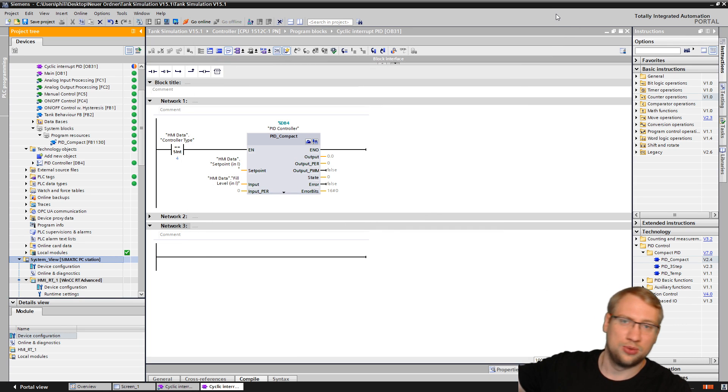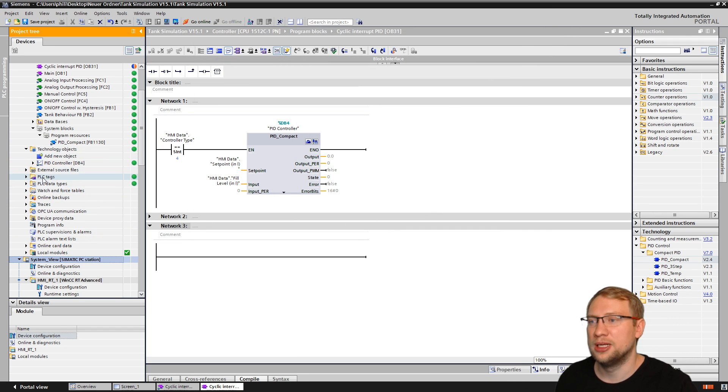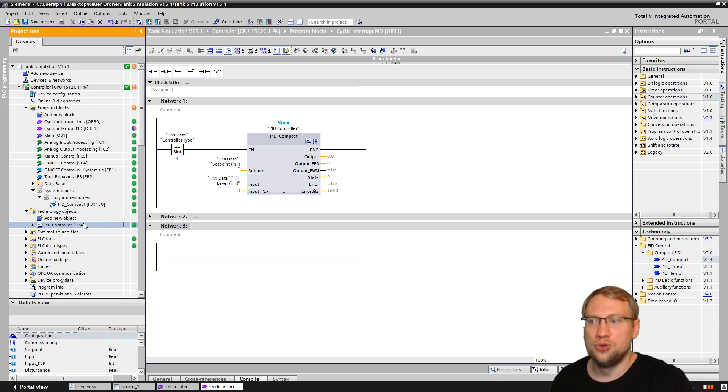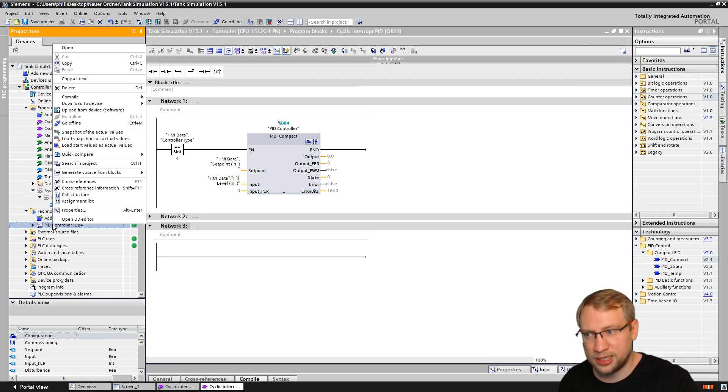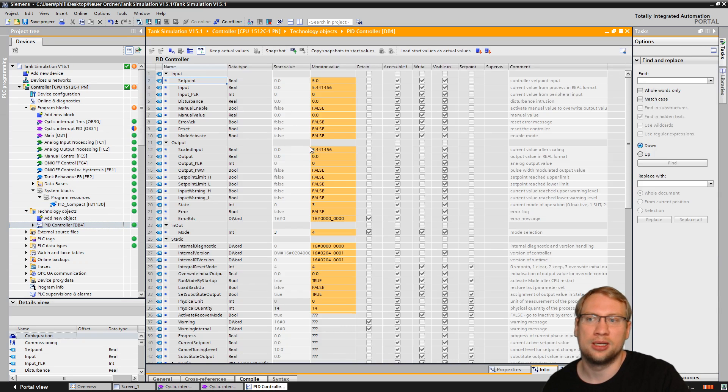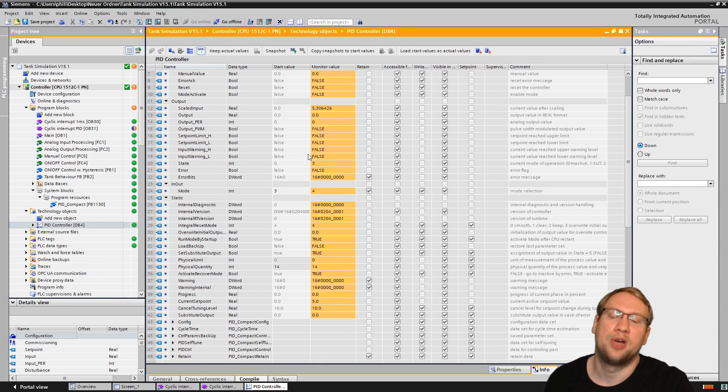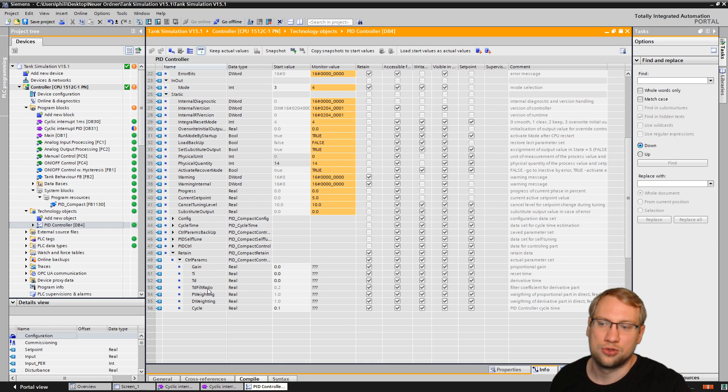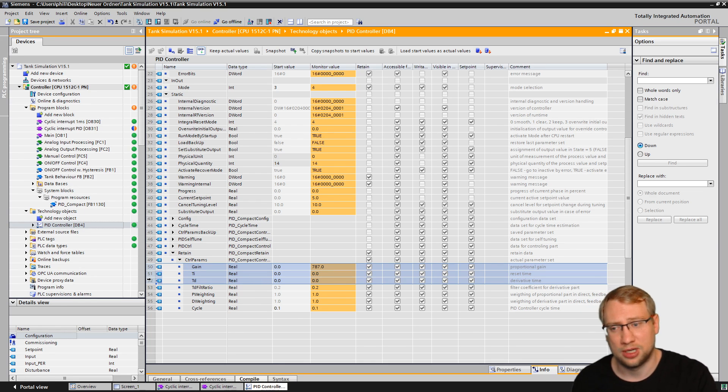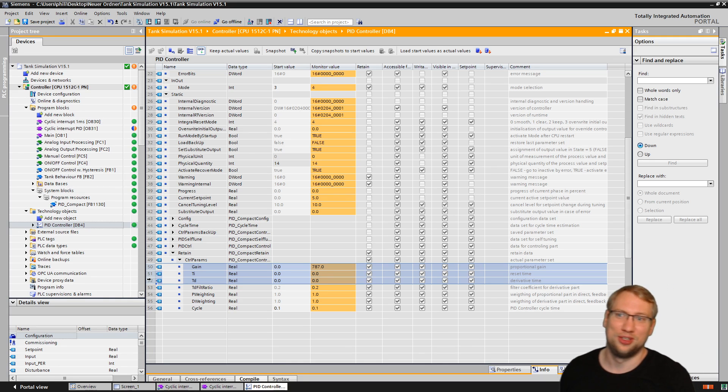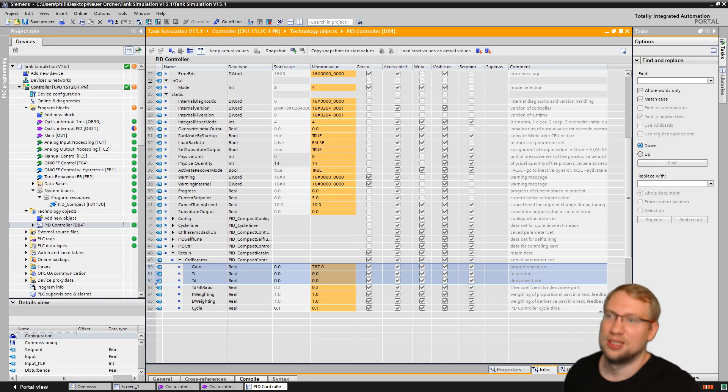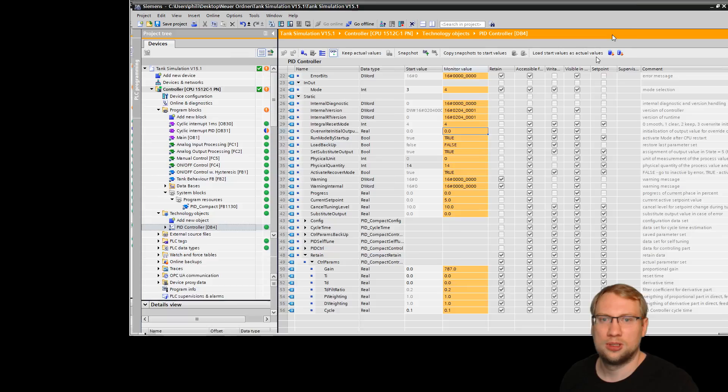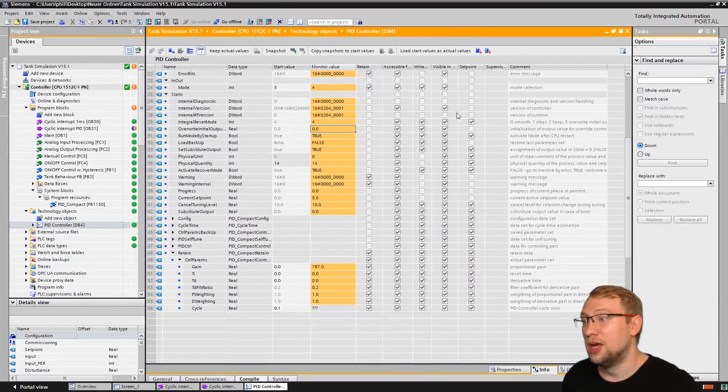That's where you find the parameters. That's where you can work with them. Just to simply repeat it: If you use the PID Compact block, just right-click on the technology object, right-click on it, and open the data block editor. And there you have all your parameters. The most important ones are the ones in retain control parameters. And there you have your gain, your reset time, and your derivative time. Of course all the others are always important, but those are the three you usually work with. And now I've changed the mode here. Mode four? Does it work? Yeah, mode four. I said that.